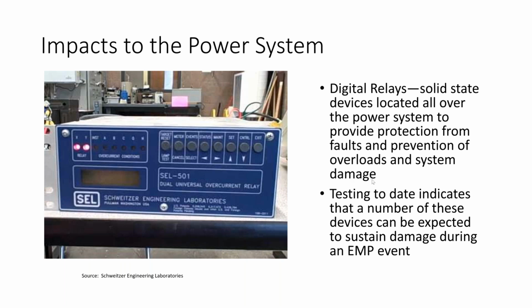What happens here in an EMP is that that device can obviously be radiated by the EMP pulse that we just talked about, and also the control cables that connect these devices, which tend to be copper control cables, will conduct energy from the pulse into the relay itself. So those are the processes, if you will, that can cause damage to the relay. So it's both radiative, that is being in the field of the pulse, but also the fact that the control wires act like an antenna and basically conduct energy from the wire into the device itself. So it's got that double kind of threat. Now, what we've learned so far, and a number of tests have been done by various people on these relays, it turns out, and I'm going to generalize here, which is dangerous, but the radiative threat is probably less of an issue for the relays than is the conductive threat.